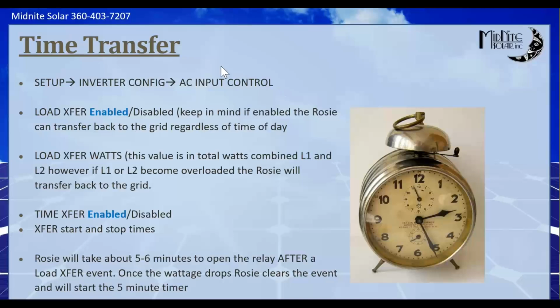but the load transfer you have to enable. So you're going to go to setup, inverter config, Rosie. I forgot a Rosie in here. AC input control, and then you're going to look for load exfer, and you want to enable that. And then you want to turn that watts up. I would turn it up to the maximum of the Rosie. There's no downside, right? So I'd turn it up to 7,000 watts on a single Rosie.